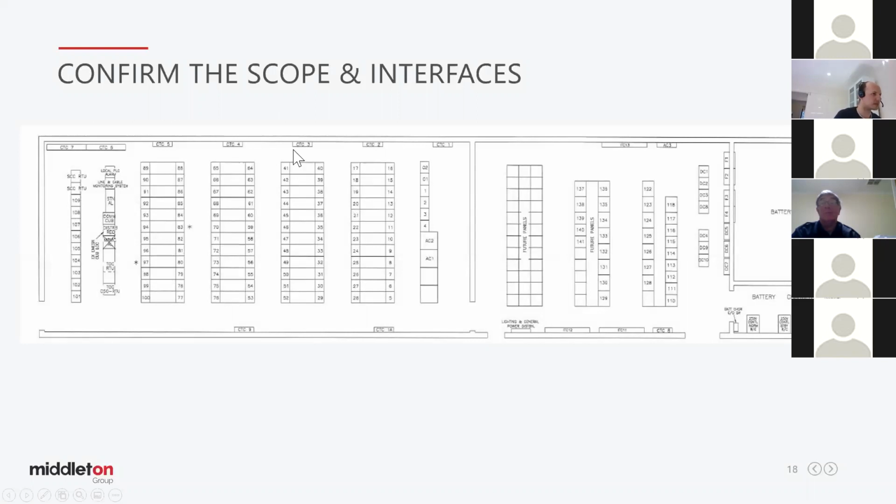The way these panels are represented here is the probably oldest style, 60s, 70s, of the panel frames, where you have one common frame throughout that area, and you've got panels mounted in on each side. This is fairly typical, and when you want to replace or install a new panel within one of these available slots, you would use what's called an SF insert panel. It's a bit smaller in terms of dimensions, but that panel would effectively slip into the existing frame and then be supported by that existing frame.